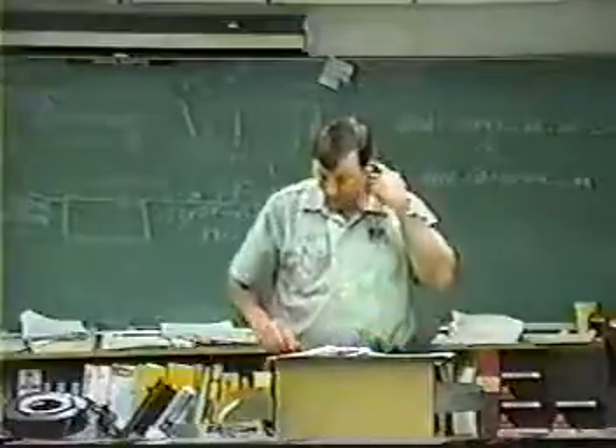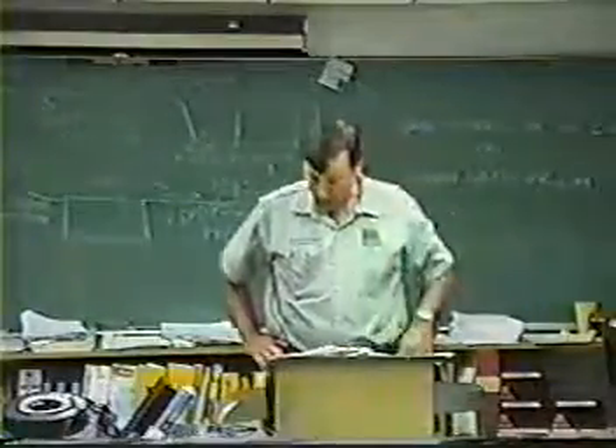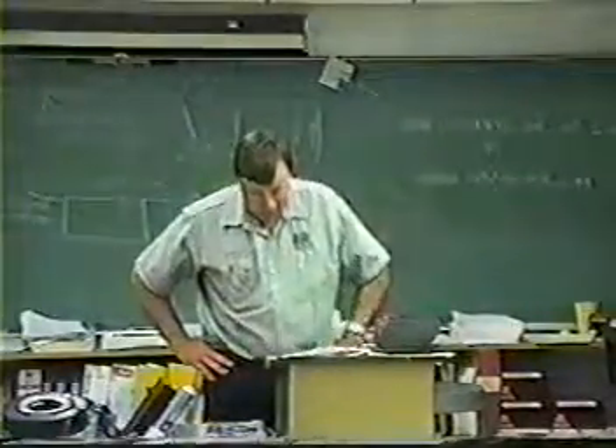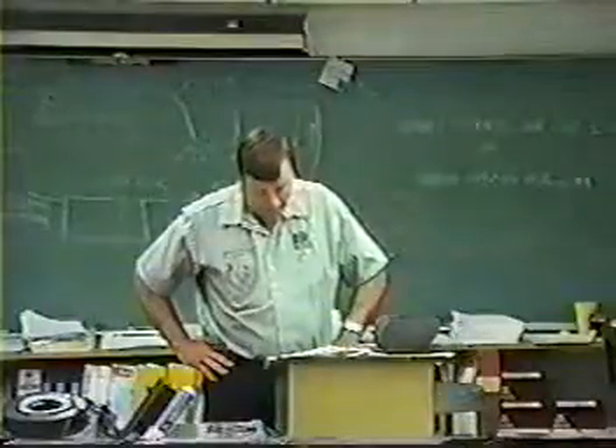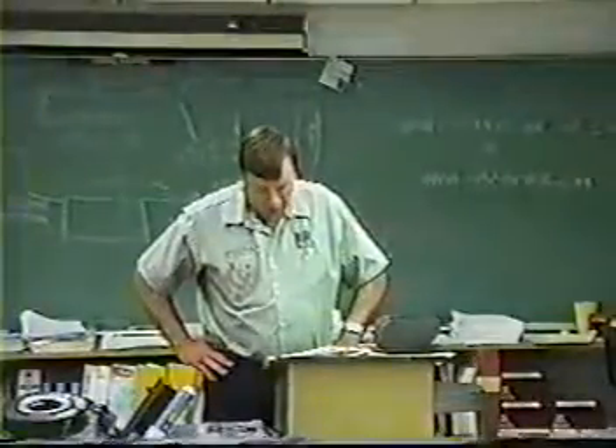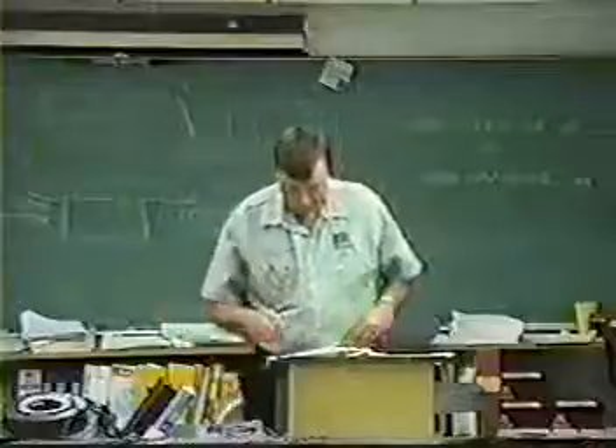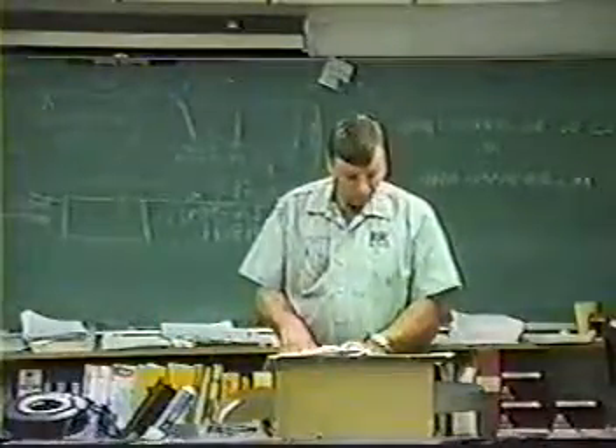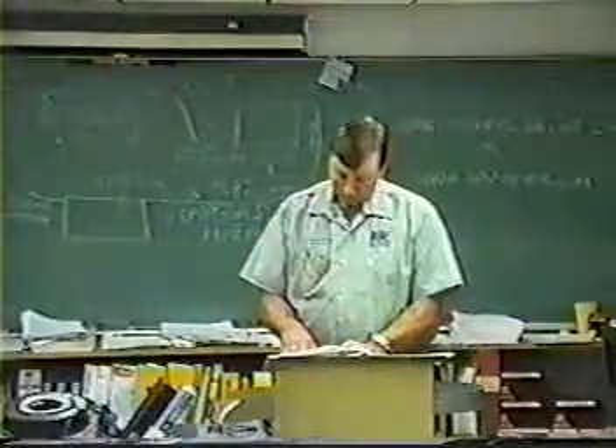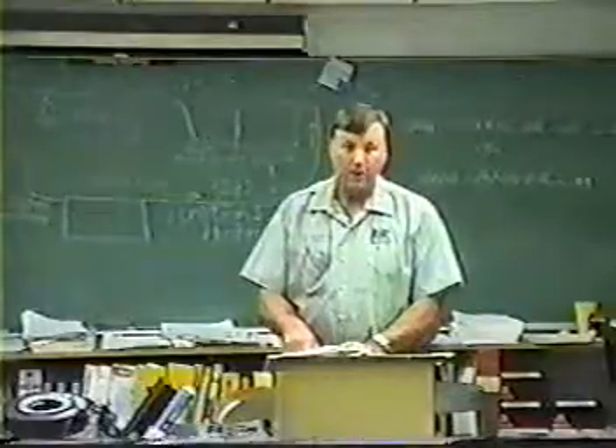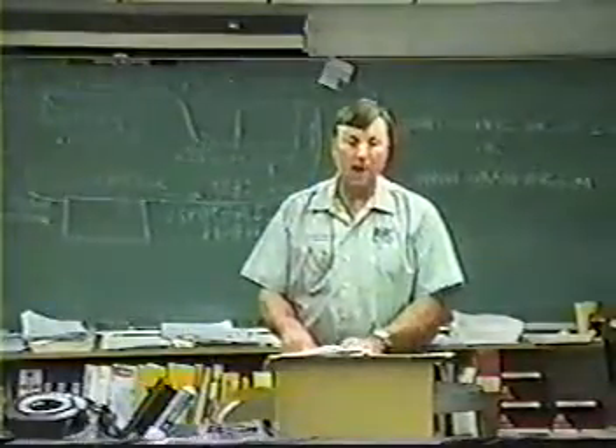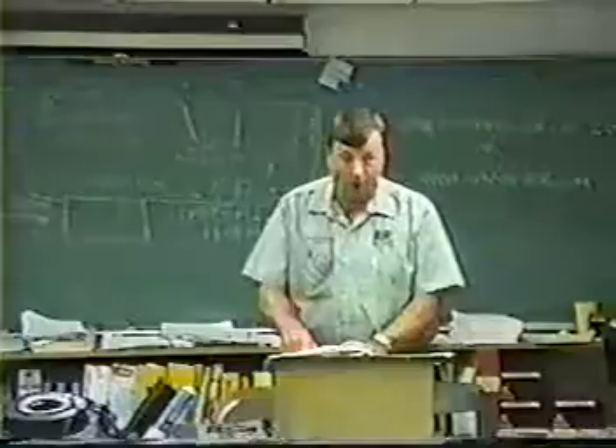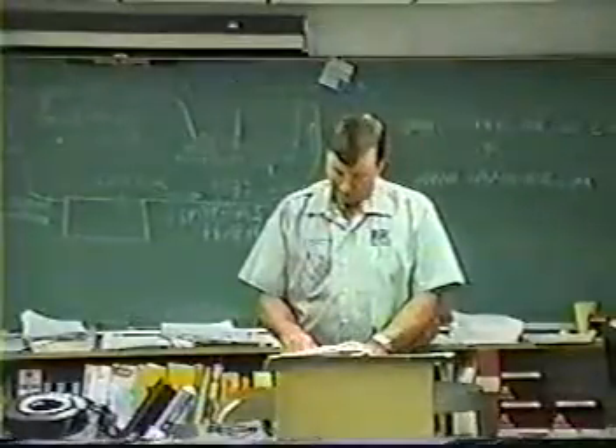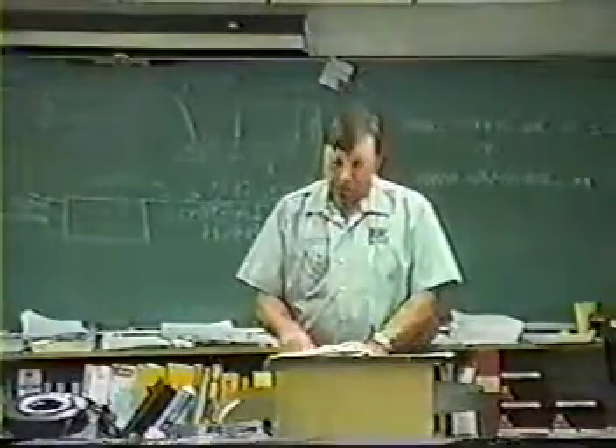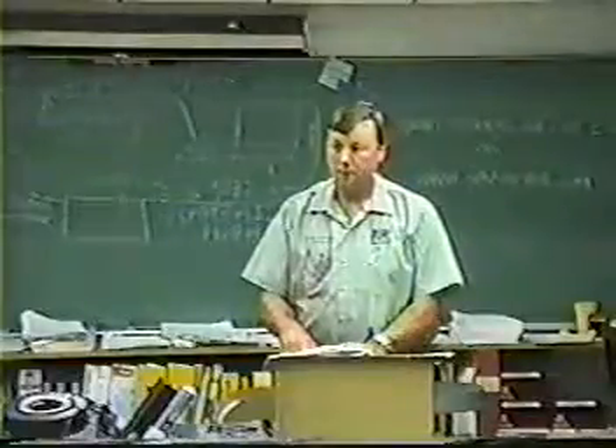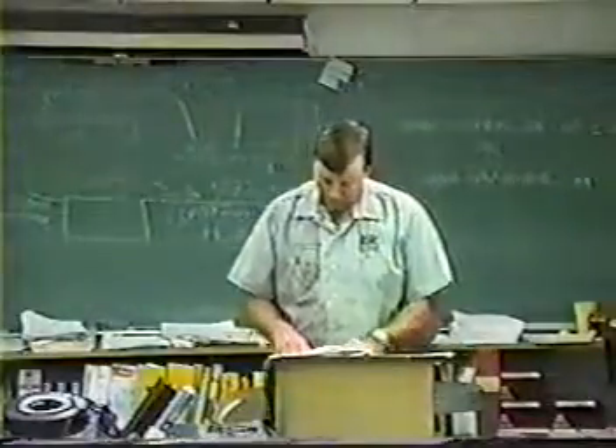Number 53. A condition of excessive superheat at the evaporator outlet and compressor inlet of an air conditioning system could be an indication of what? Low charge. B. Low refrigerant charge. We talked about superheat readings, didn't we? We talked about a high superheat could be low in freon. Low in refrigerant charge. Does anybody not see that one now? We're going to number 54.